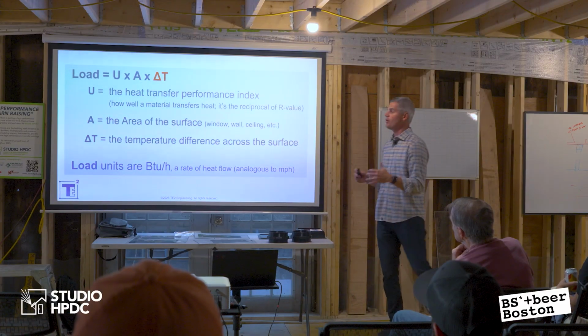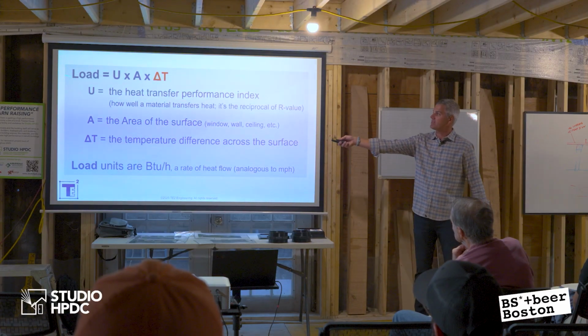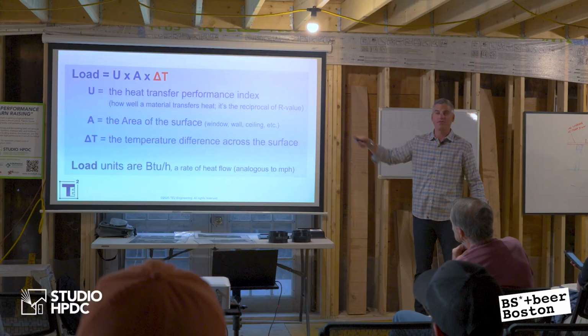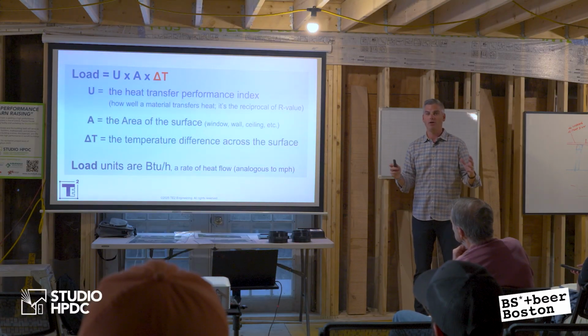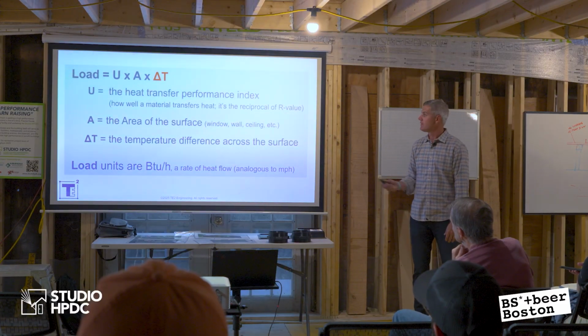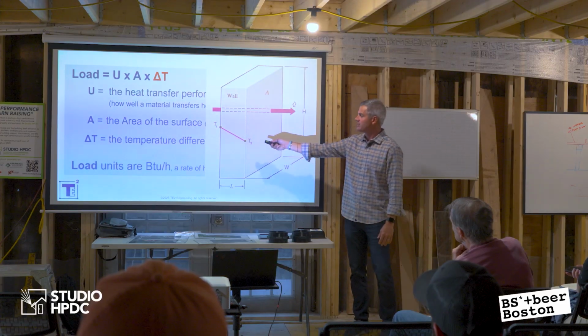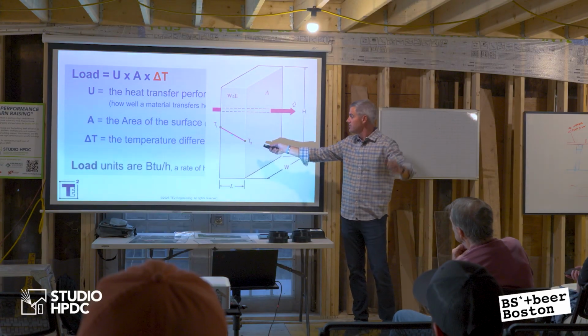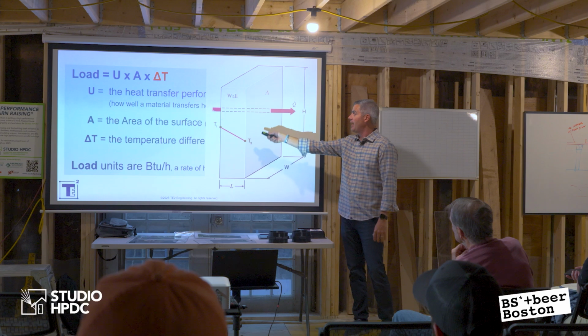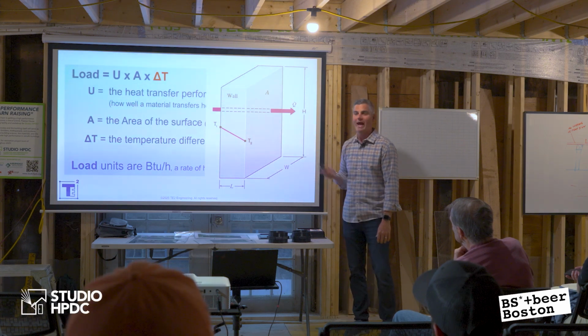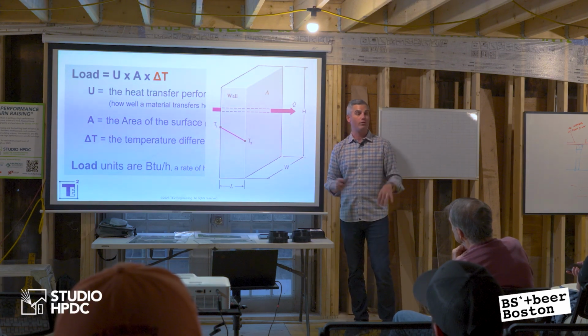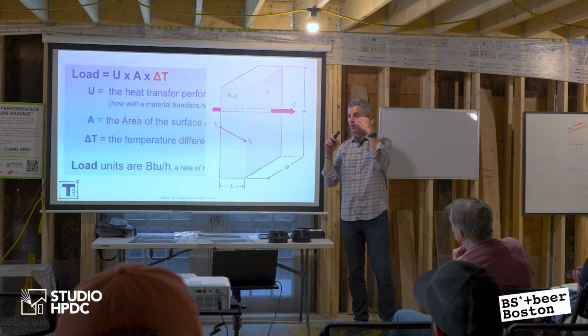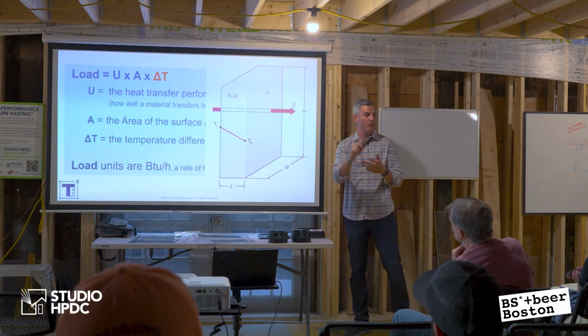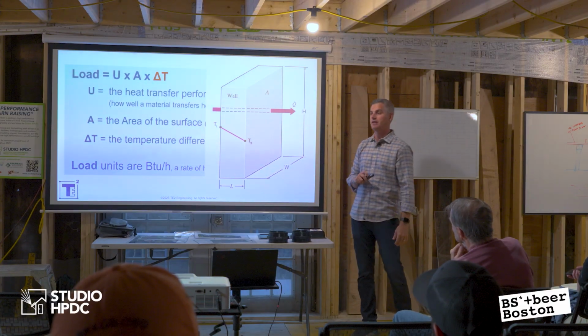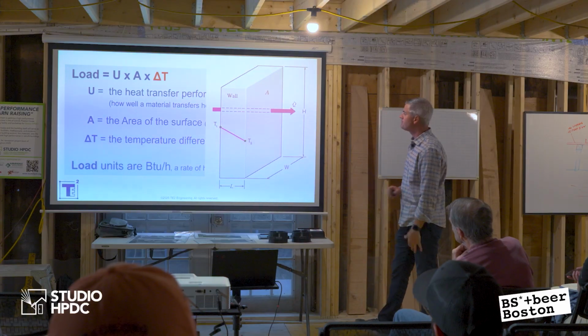So what does that software do when you do a Manual J? It's calculating a load based on UA delta T. It's doing a million of these conductivity equations. That means if I have a wall, with temperature outside maybe 88 degrees and temperature inside maybe 75 degrees, I'm going to have heat flow, heat gain, heat transfer added to the building. And that's what that software is doing across every wall, every window, every roof, every floor, every assembly in that building. It looks at the entire outside.